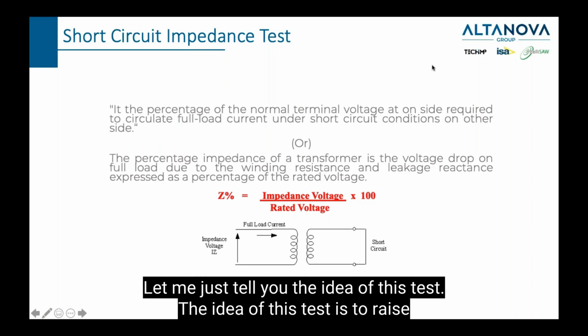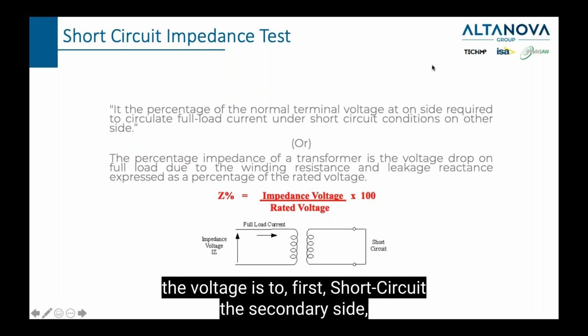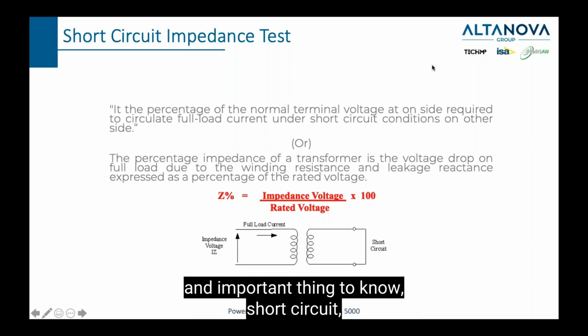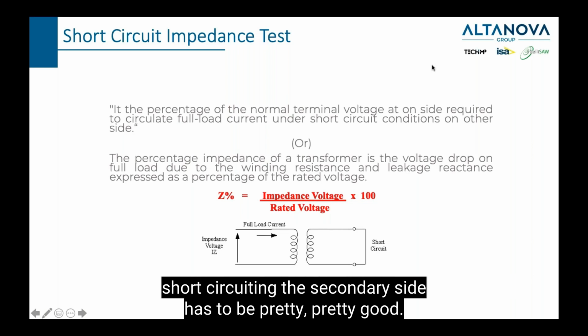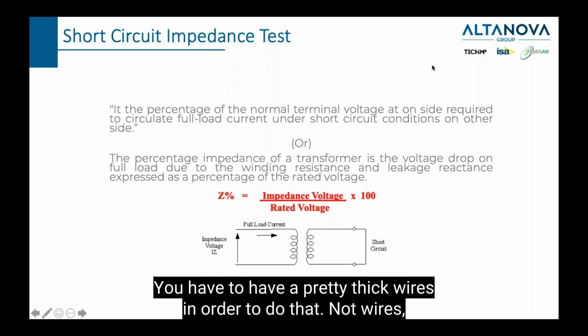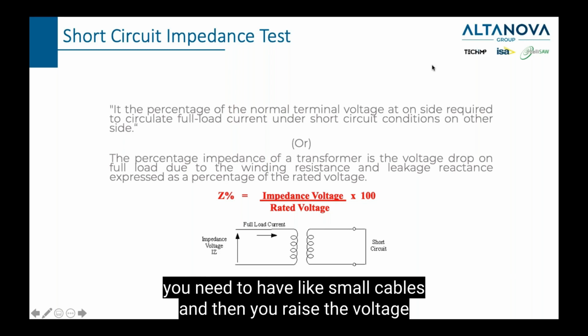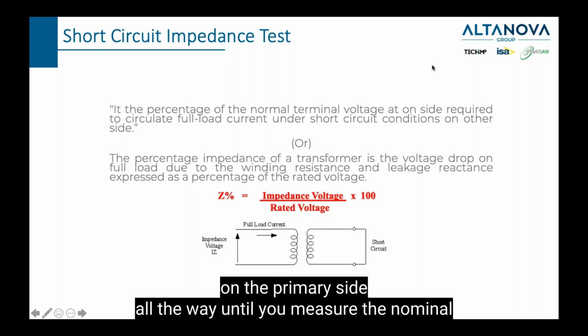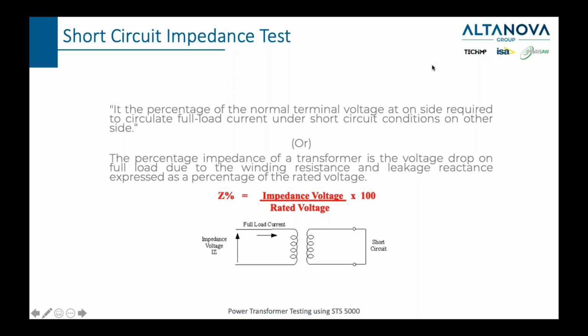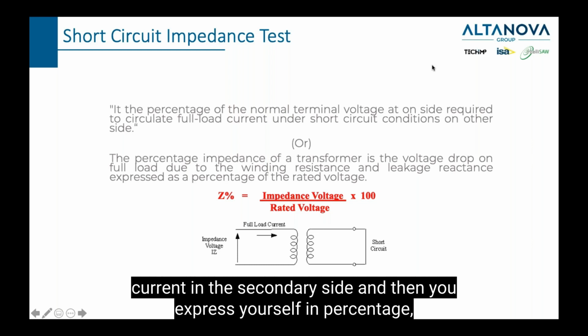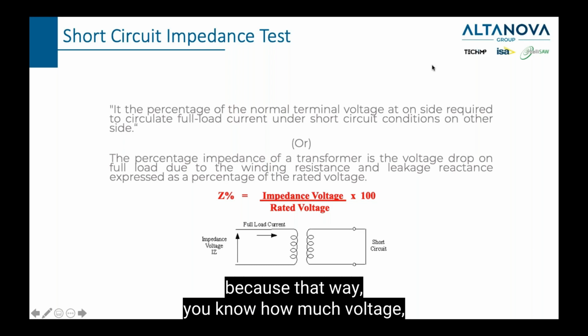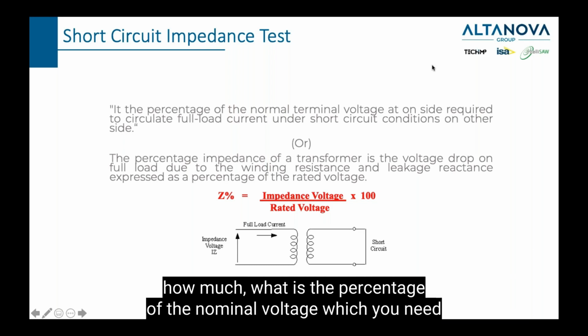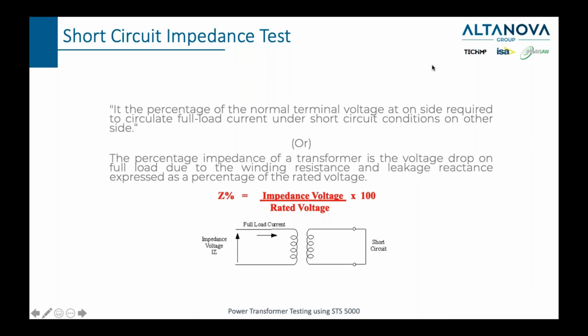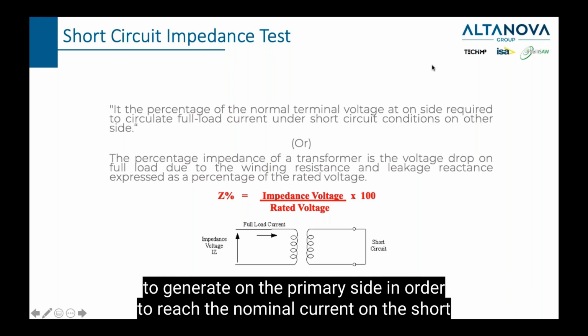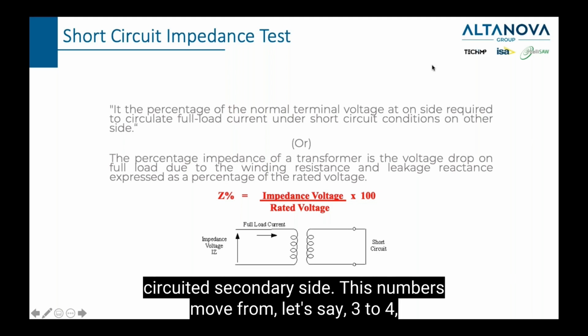The idea of this test is to first short circuit the secondary side. An important thing to know is that the short circuit of the secondary side has to be pretty good. You need pretty thick wires, actually small cables, to do that. Then you raise the voltage on the primary side all the way until you measure the nominal current in the secondary side. And then you express it in percentage, because that way you know what percentage of the nominal voltage you need to generate on the primary side in order to reach the nominal current on the short-circuited secondary side.